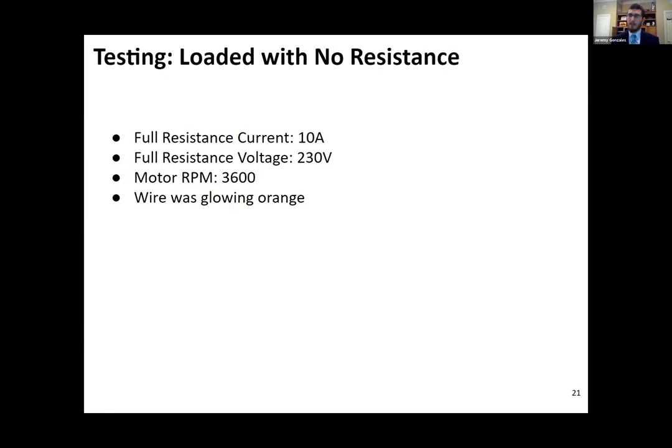This test was loaded with minimum resistance on the rheostat. And once it got going, as you can see, it had a full load current of 10 amps and a full load, full resistance voltage of 230 volts, meaning that when the device had finally finished its startup phase, it was running as intended. And as you can see, it was running at the expected speed of 3,600 RPM. However, the last little bit of the rheostat was glowing orange, indicating that it was having some minor to major heat issues.